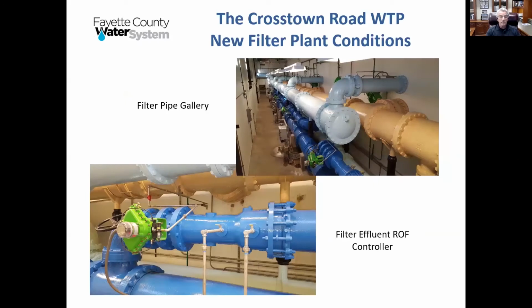There are more shots of it here. You're looking at an effluent rate of flow controller there with the K-Tork pneumatic actuator on it and the Venturi tube. It sure looks a lot better than, I didn't do contrasting pictures, but I could have and showed you the difference, but we've really cleaned that up. But one thing you'll notice as you look down through that filter pipe gallery is there's not a lot of conduit wiring because there's no 480 volt power distribution system to the pneumatic actuators, and there's little to no conduit wire coming down from the consoles above to get to all of the instrumentation and to get to the actuators.